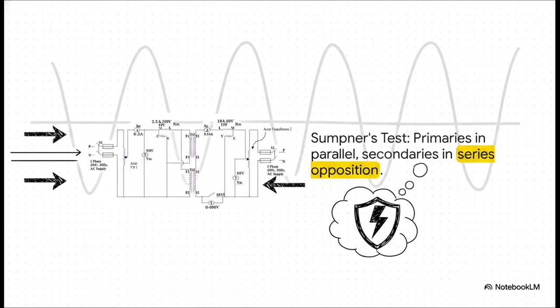This is the magic arrangement. One is trying to push voltage one way, and the other is pushing back with the exact same force. And here is the absolute genius of this test. The first power supply provides the rated voltage, which takes care of the core or idling losses for both transformers. Then a second supply injects just a small voltage into that secondary loop, but it's enough to circulate the full load current through the windings of both machines, creating the full load copper losses. They are both running at full load conditions, getting hot, getting stressed, but the only power you're actually drawing from the wall is the tiny amount needed to cover their combined energy losses.